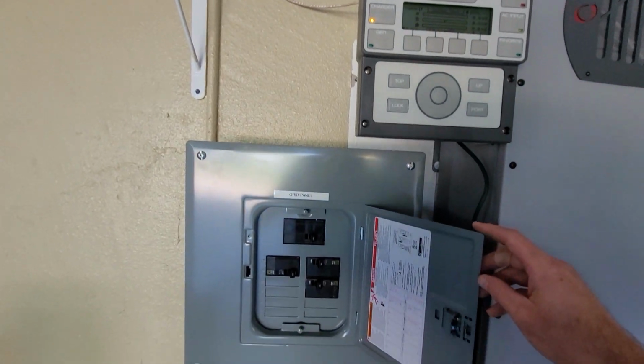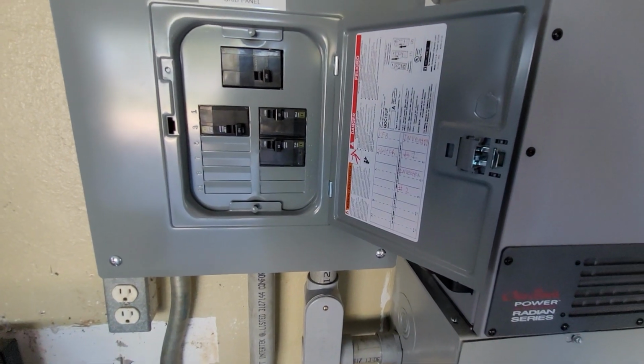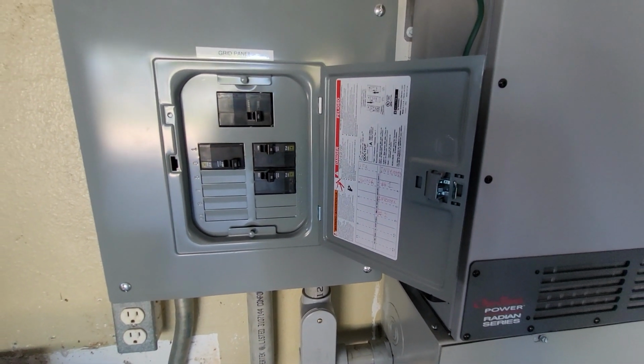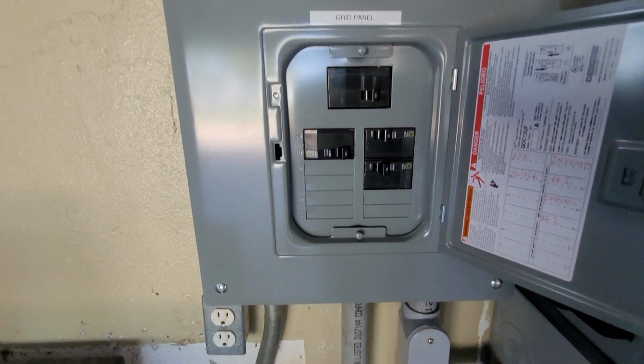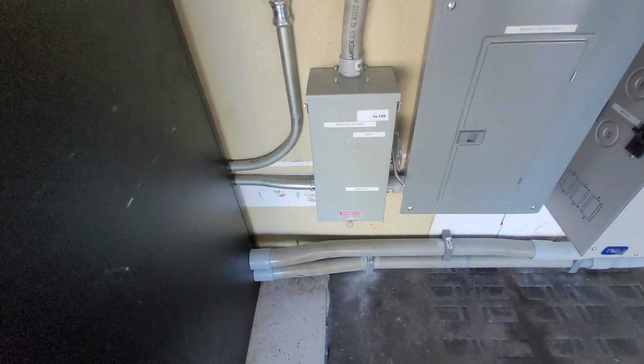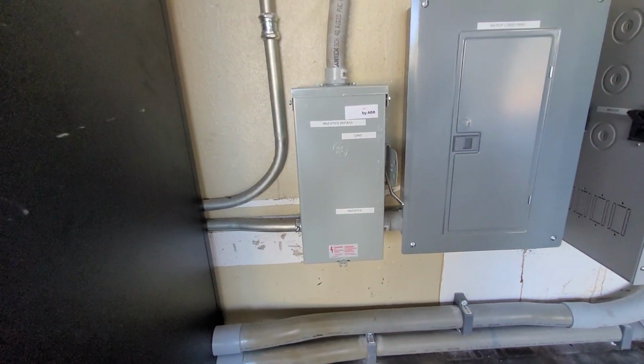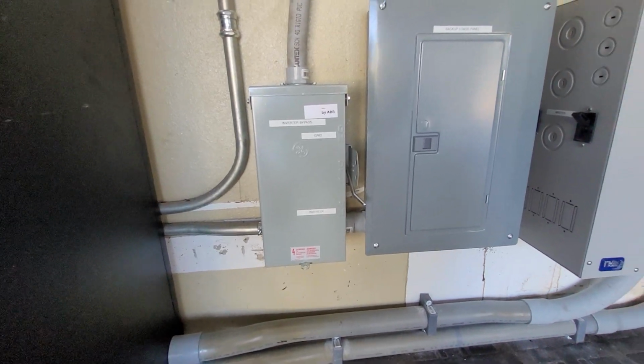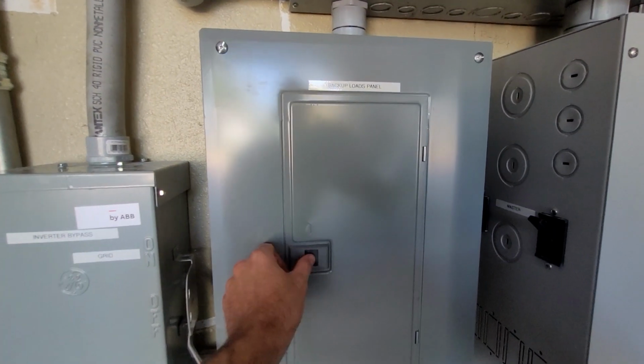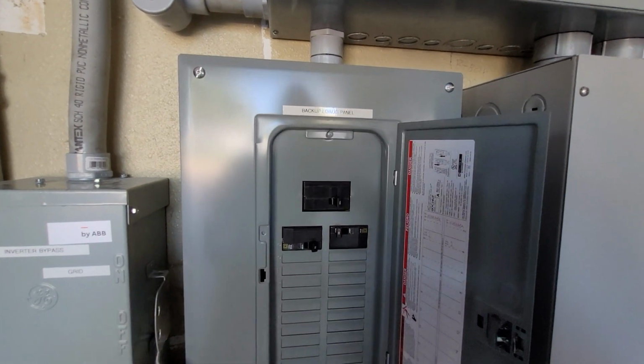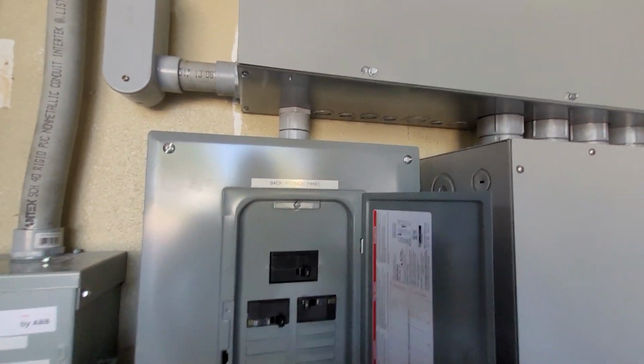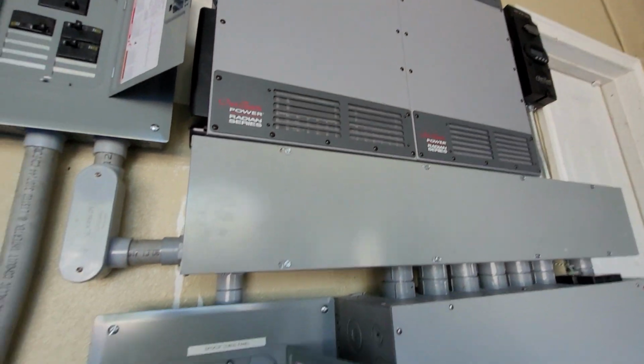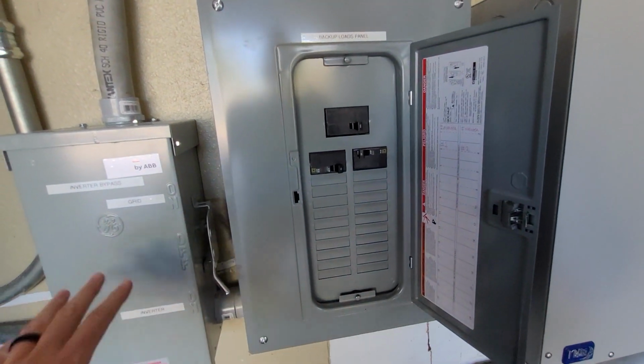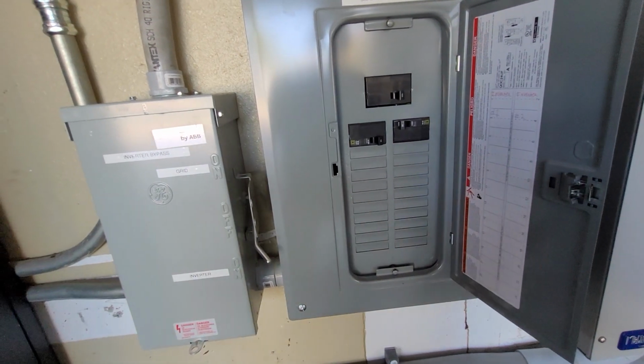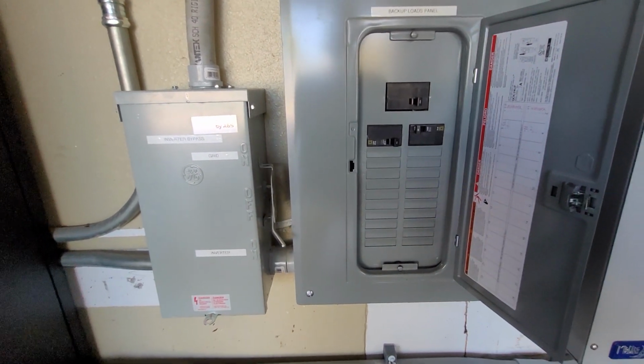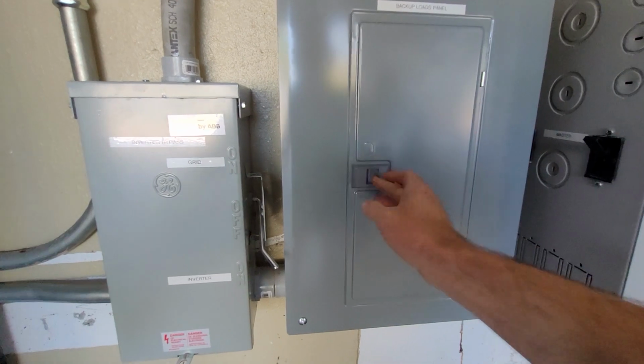And what we did here is just aggregate the feed from the grid to both of these inverters. And then this 100 amp goes down to this transfer switch, which just lets us bypass these inverters for service and if there's an issue. And then this backup loads panel here is just aggregating the output of these two Radians into this panel and then sends it to the transfer switch, which then goes to the panel next to the existing main panel.